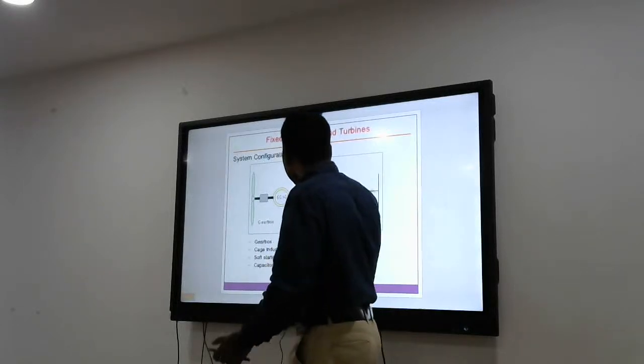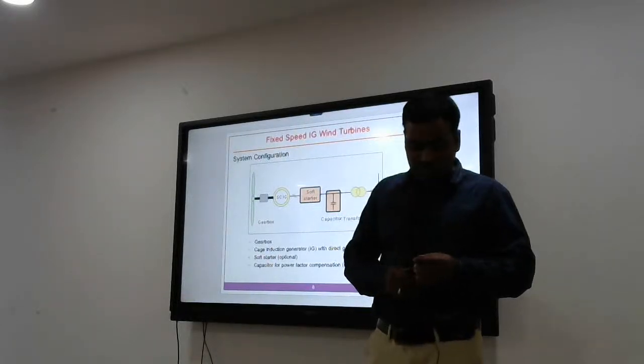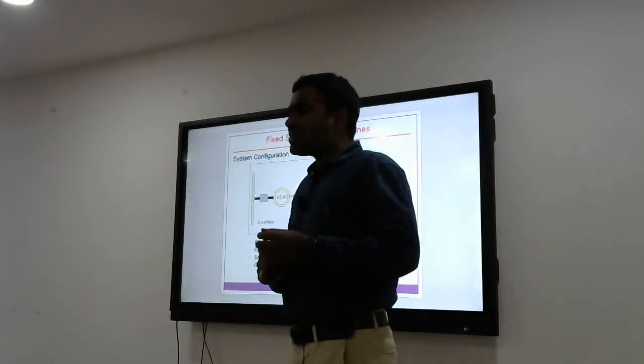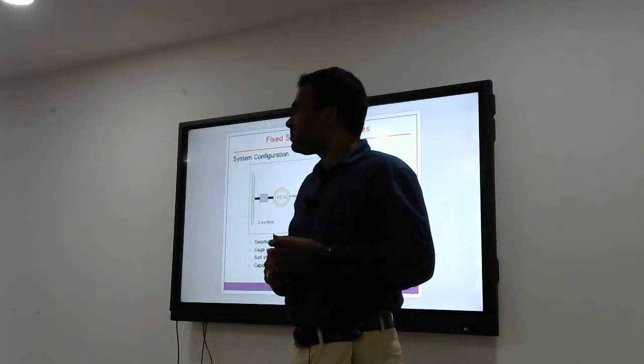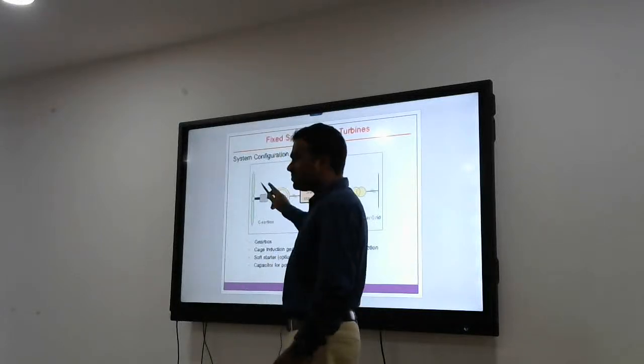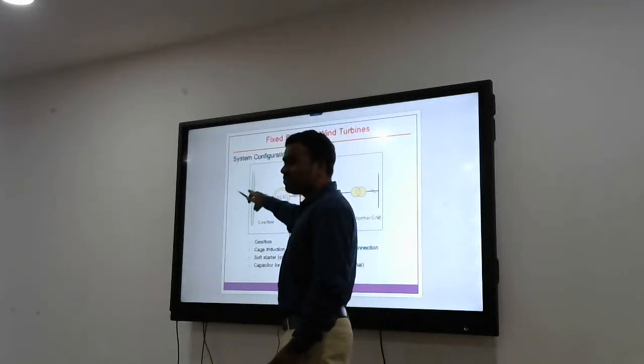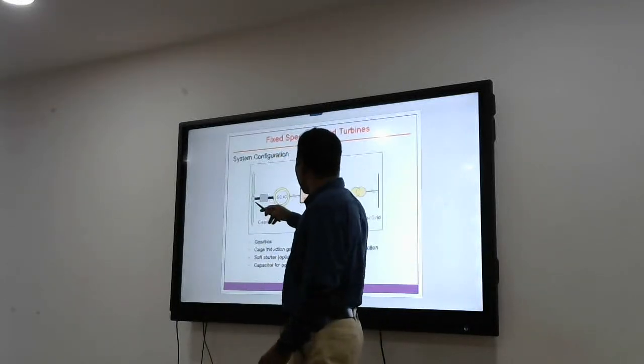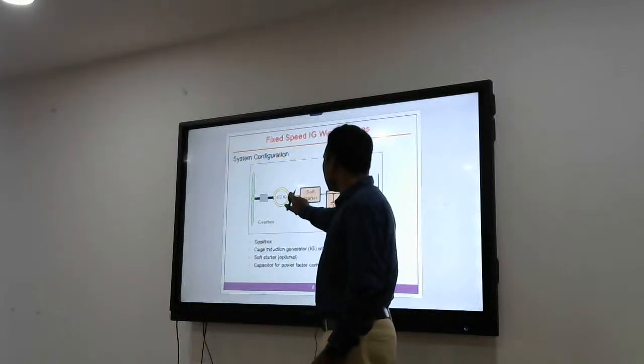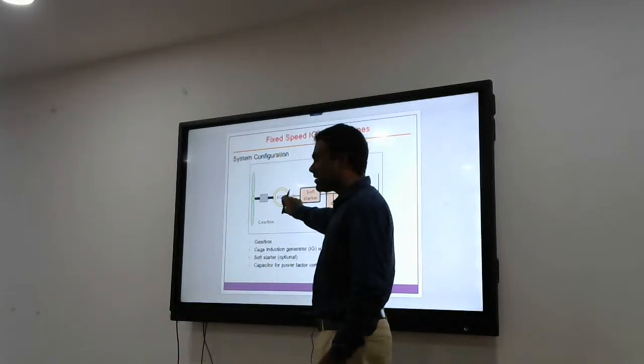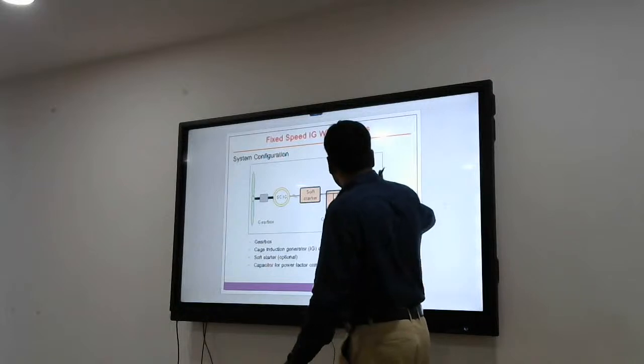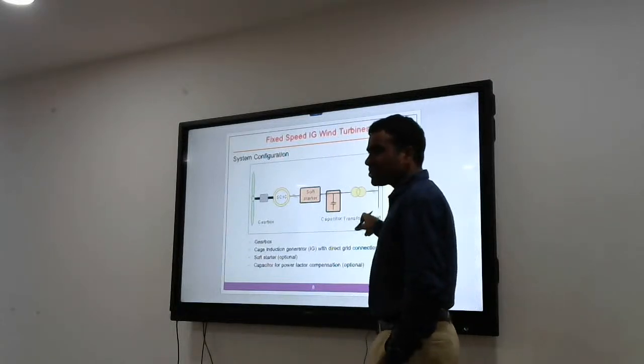Okay. Just if we see fixed speed wind turbines now. In fixed speed wind turbines, this is a squirrel cage induction generator. This was coupled to the wind turbine. And if you see the stator, that was almost directly connected to the grid. This is the grid, almost directly connected to the grid.